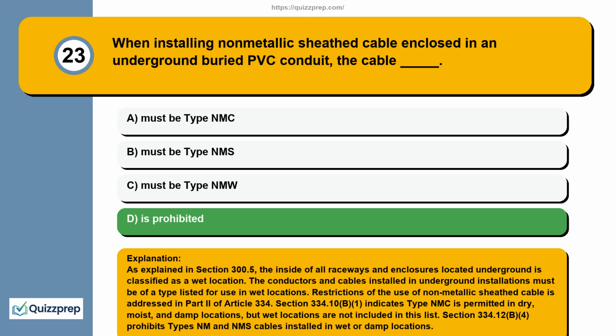As explained in Section 300.5, the inside of all raceways and enclosures located underground is classified as a wet location. The conductors and cables installed in underground installations must be of a type listed for use in wet locations. Restrictions of the use of non-metallic sheath cable are addressed in Part 2 of Article 334. Section 334.10(B)(1) indicates type NMC is permitted in dry, moist, and damp locations, but wet locations are not included in this list. Section 334.12(B)(4) prohibits types NM and NMS cables installed in wet or damp locations.